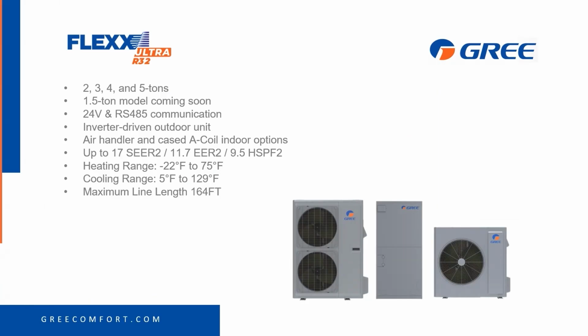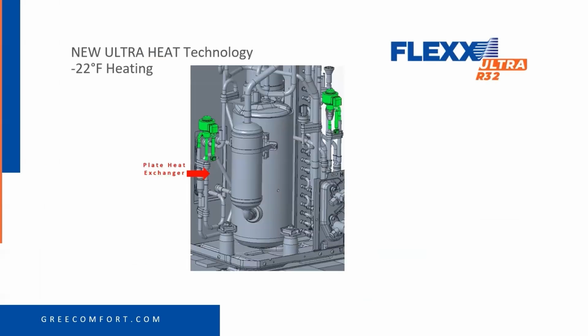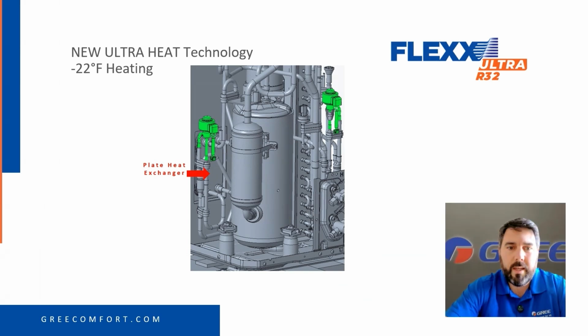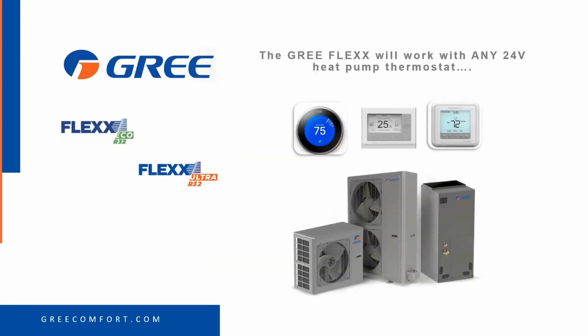Up to 17 SEER, 9.5 HSPF2. The heating range is down to -22, and the cooling range is down to 5 degrees without any additional, like a low ambient kit. So just kind of getting into the technology just a hair. It's a different type of technology than we've seen in the past with the Ultra Heat. And what it's using is a plate heat exchanger. And then instead of just an open closed solenoid to inject the hot gas back into the compressor, it's using an EEV.